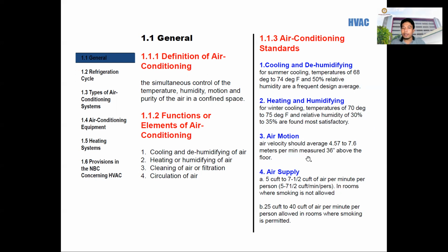Next is air motion. Air velocity should have an average of 4.57 to 7.6 meters per minute, measured 36 inches above the floor.